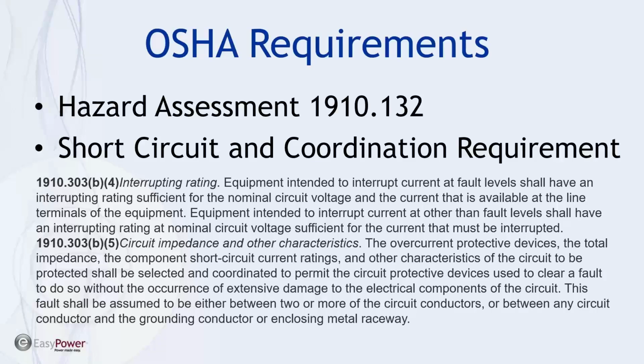And of course, to determine what your current ratings are and make sure they're going to be sufficient for the current, you have to know what the fault current is. Hence, you do a short circuit study. And then circuit impedance and other characteristics. And these are titles that are misleading. One is interrupting rating, one is circuit impedance and other characteristics. So you don't just look at these and say, geez, this means I have to do a short circuit and coordination study, but that's really what it comes down to.